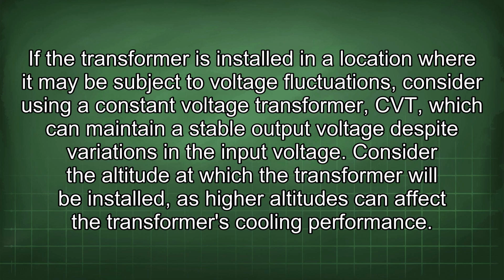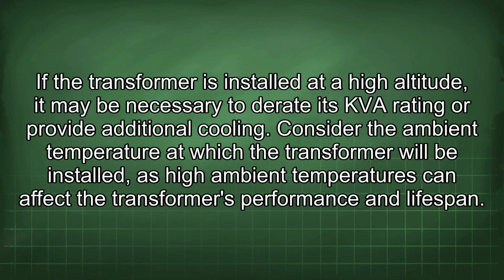If the transformer is installed in a location where it may be subject to voltage fluctuations, consider using a constant voltage transformer, CVT, which can maintain a stable output voltage despite variations in the input voltage. Consider the altitude at which the transformer will be installed, as higher altitudes can affect the transformer's cooling performance. If the transformer is installed at a high altitude, it may be necessary to lower its KVA rating or provide additional cooling.